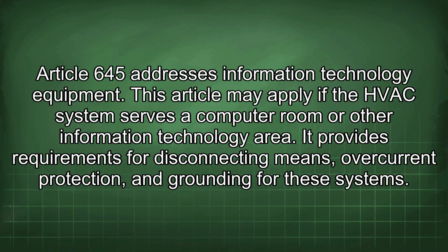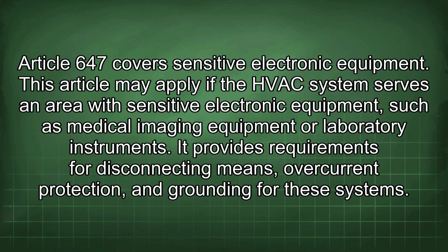Article 645 addresses information technology equipment. This article may apply if the HVAC system serves a computer room or other information technology area. It provides requirements for disconnecting means, overcurrent protection, and grounding for these systems. Article 647 covers sensitive electronic equipment. This article may apply if the HVAC system serves an area with sensitive electronic equipment, such as medical imaging equipment or laboratory instruments. It provides requirements for disconnecting means, overcurrent protection, and grounding for these systems.